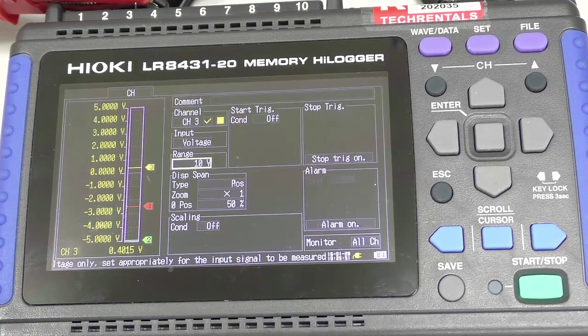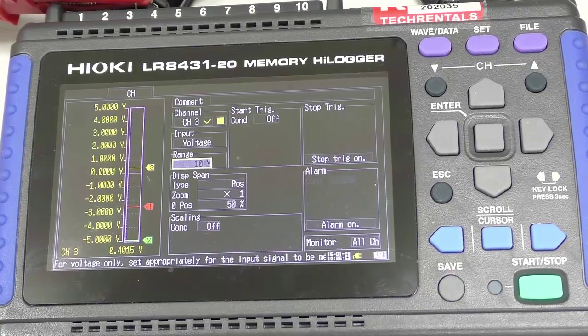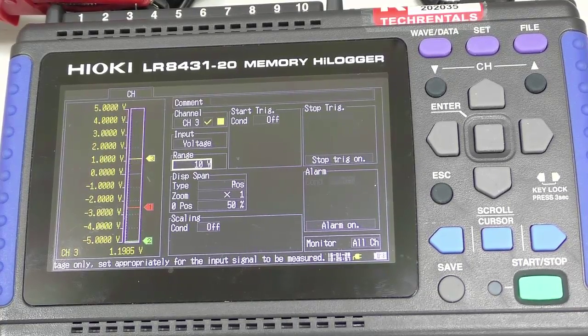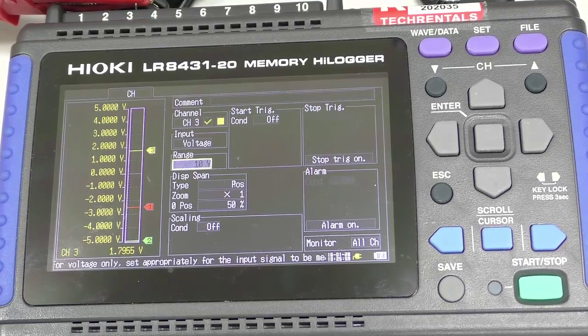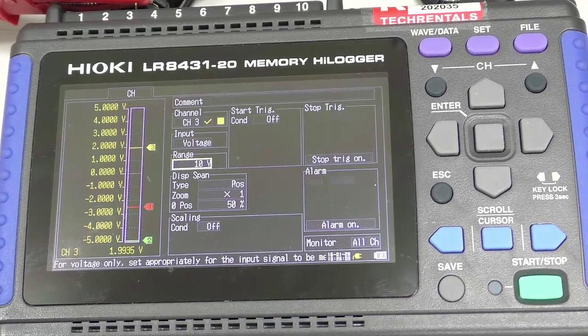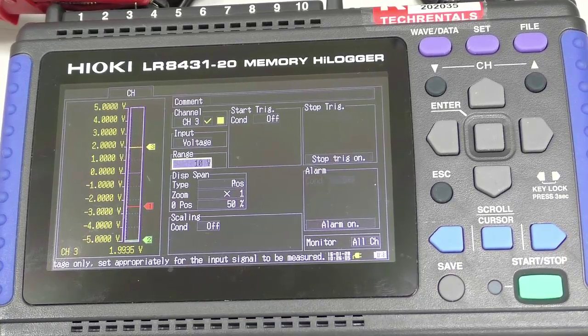I've written that down and I'm going to set the calibrator up to 20 milliamps. My high value at 20 milliamps — that's my 100% value — reads 1.9935 volts.